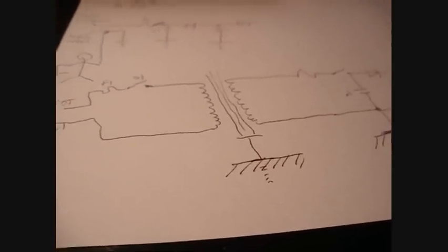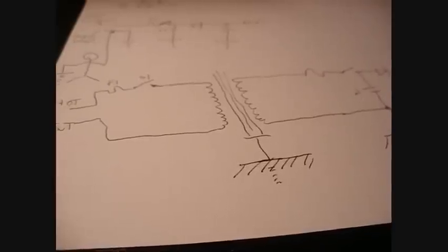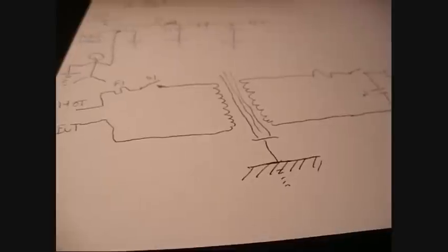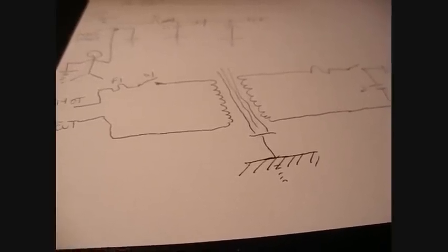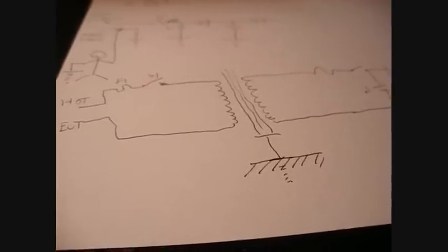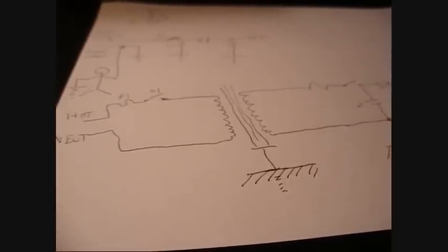Now I will give you a word of caution, and this is especially true with a lot of older tube-type black and white televisions, and probably some cheapo color sets too. Just because you see the presence of a power transformer on the chassis, that does not necessarily mean you have a cold chassis TV. For example, I've got a Crosley TV that you're going to see a video of one of these days. It's from about 1953, and the transformer in that set is simply just an autoformer that is used to supply voltage to the tube filaments, but the B+ voltage is derived straight from the power line.